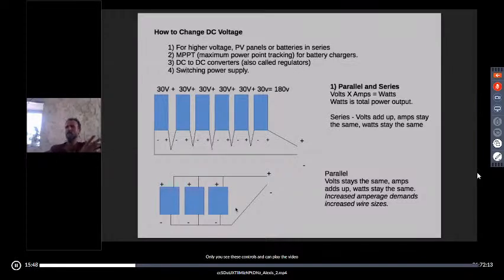So the panel's putting out around 30 volts. That's okay for a 24 volt motor. We get enough amperage to run the motor, but you have to pay attention. You can look it up online, wire sizes. If you're an electrician, you kind of know it in the back of your head in terms of what wire will handle what amperage. But certainly when you start doing things in parallel, you need to think about wire sizes.